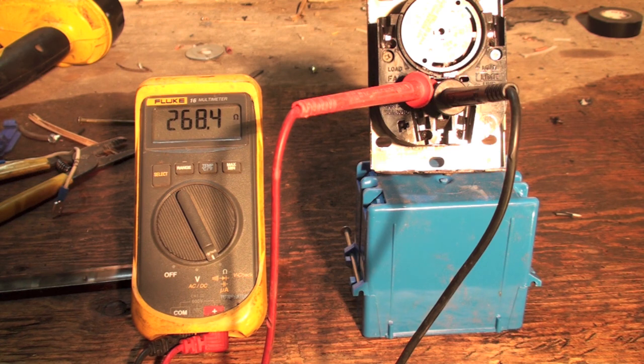When the furnace first starts up, the return air is going to be cold, and so the fan switch has come on, but oftentimes enough cold air comes in to kind of shock that switch and actually turn it down enough to shut it off. You've got to set it maybe 140 and 110, or 140 and 100, something like that. And sometimes it'll shock it and turn it off, so they put a little heater in there.